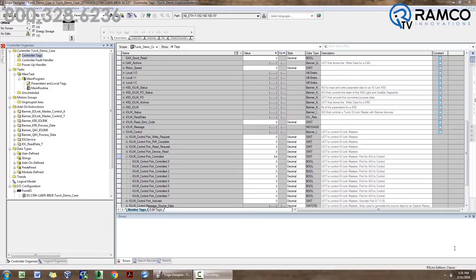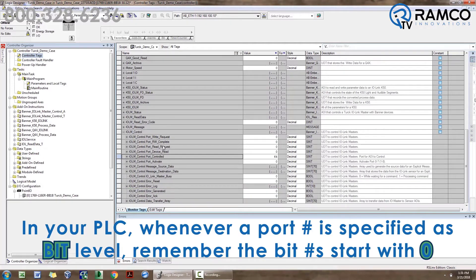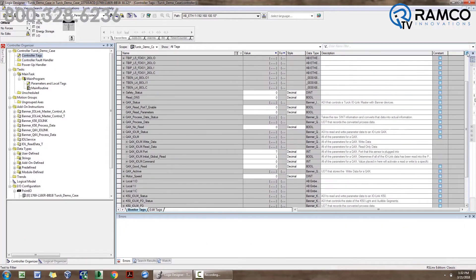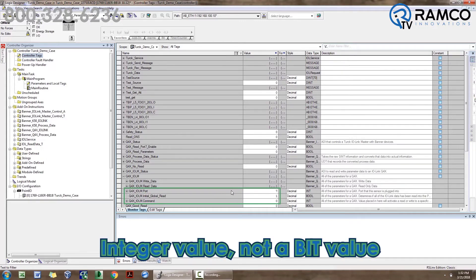A few gotchas to be aware of as you set up this connection. In your PLC, whenever a port number is specified as bit level, remember the bit numbers start with zero, so the port number you enter may be off by one. For example, my sensor is connected to port 7 on the Turck block, so I'm specifying bit 6 for port controlled, port active, port re-request, write request, RW complete, and port device read. In the Q4X parameter data function block, the port controlled is an integer value, not a bit value, so you put in the actual port number you're controlling. In my example, I entered 7 for port 7 on the Turck block.